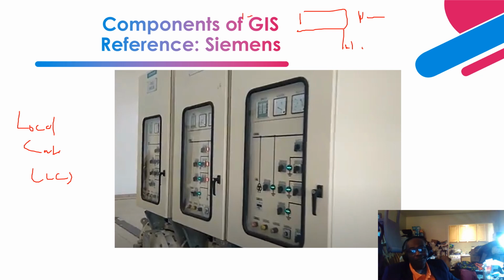Transmission line, and the GIS, and your SCADA system, right? And any downstream, your line side equipment, like any feeder that is going to the load, right? The customers, right? Any equipment. If you have a switchgear that is there, medium voltage, it goes through a power transformer, steps it down to a medium voltage switchgear. All of it, the interlocks are all tied to this one.